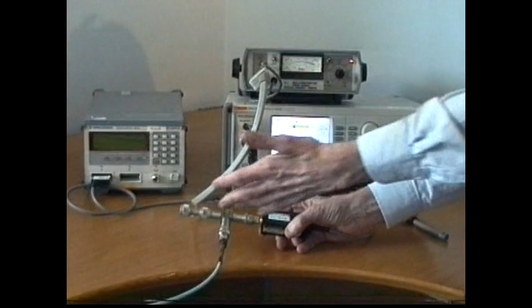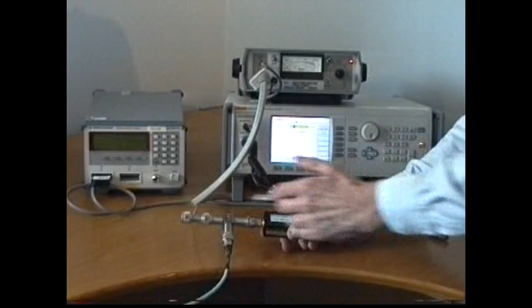In this short video we are going to demonstrate how to use a 9640 to perform a flatness or frequency response calibration for an RF millivoltmeter. To perform this calibration traditionally you would need to use a power meter and power sensor as a calibration standard, such as we see here, with the signal being produced by a signal generator coming into a splitter sharing the signal between the power sensor and the RF millivoltmeter input.